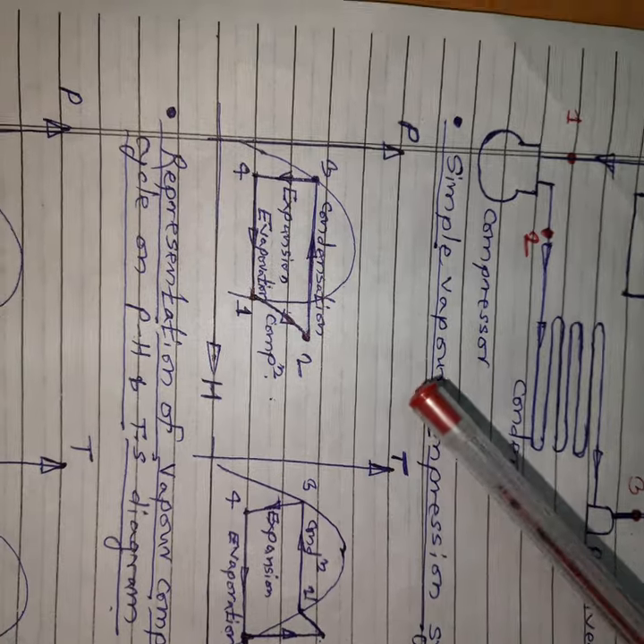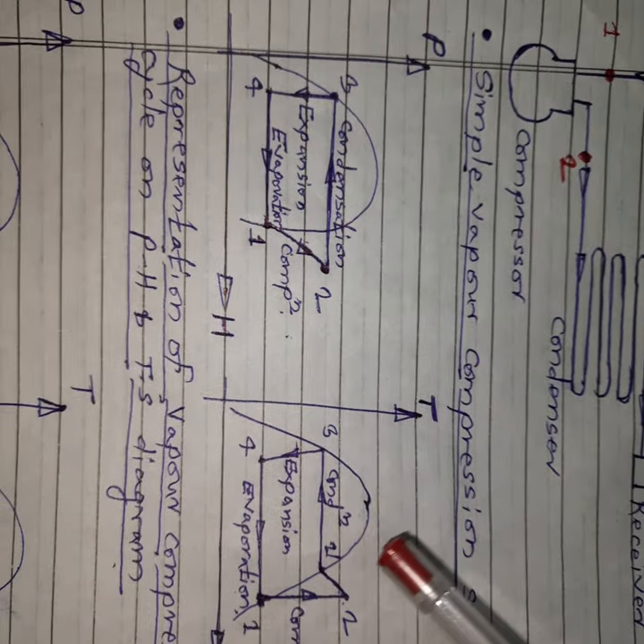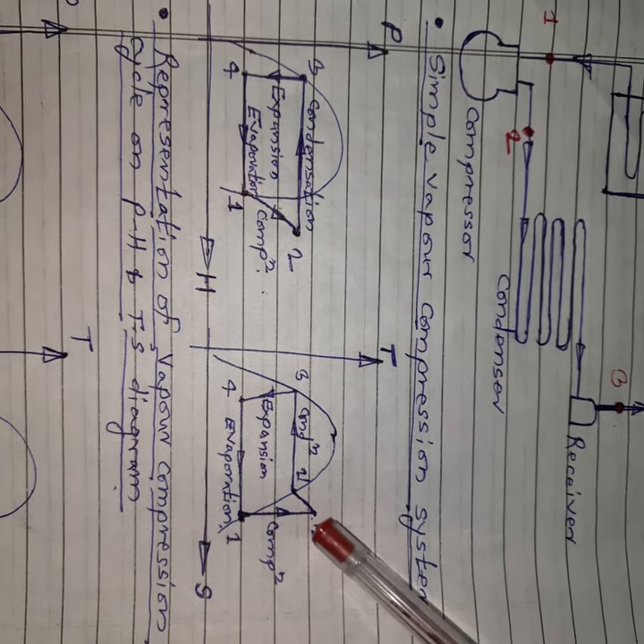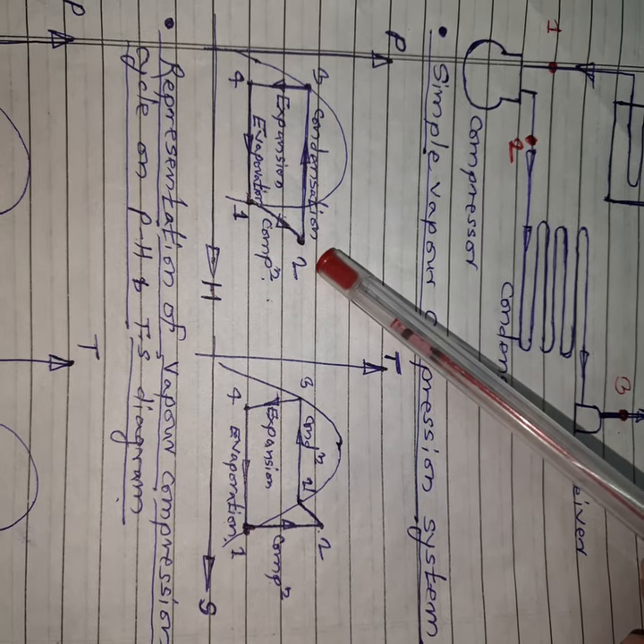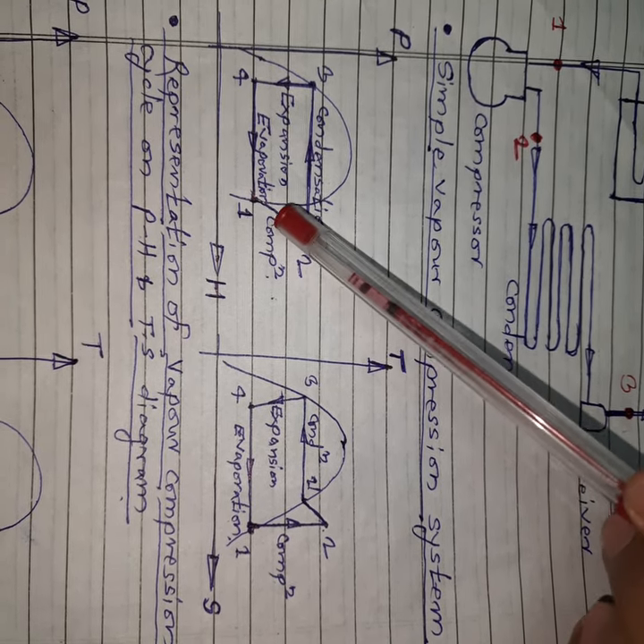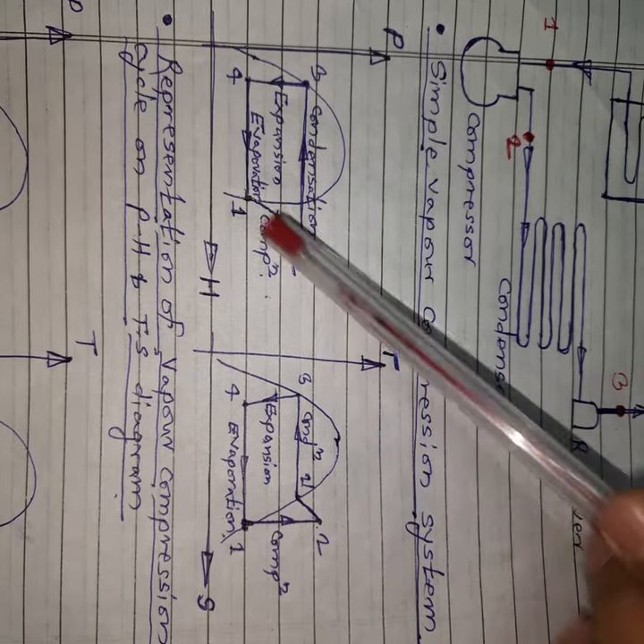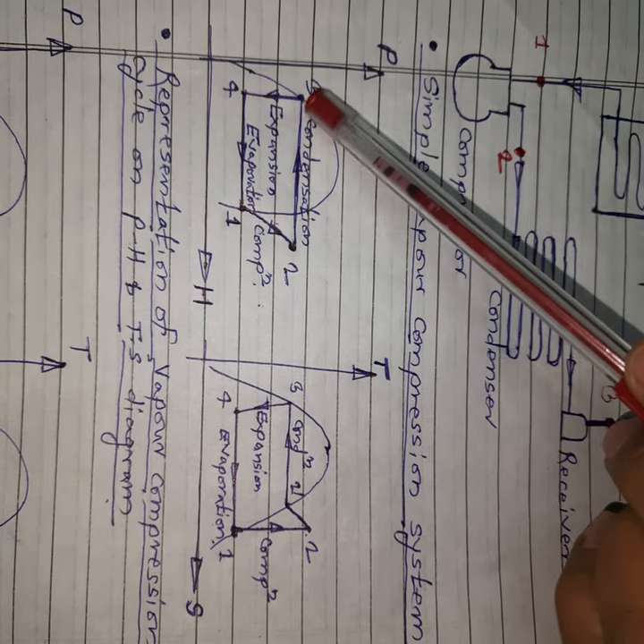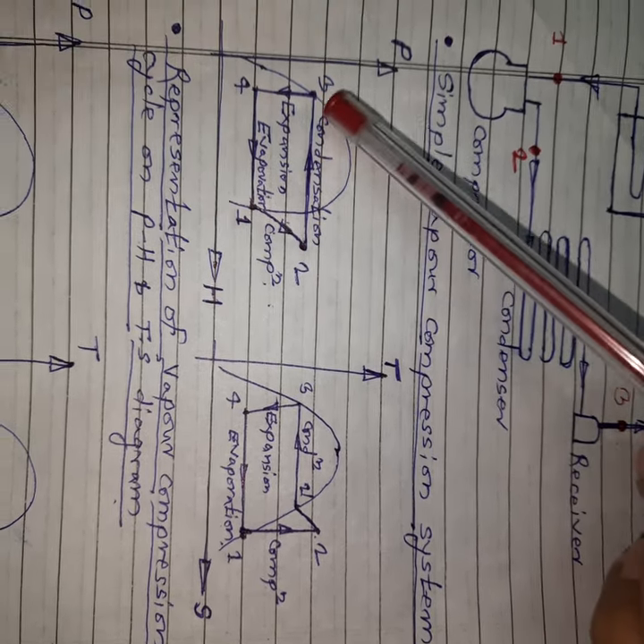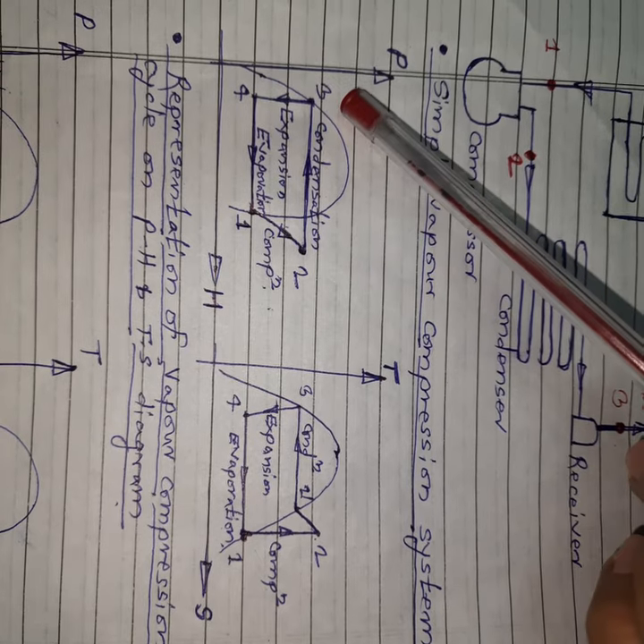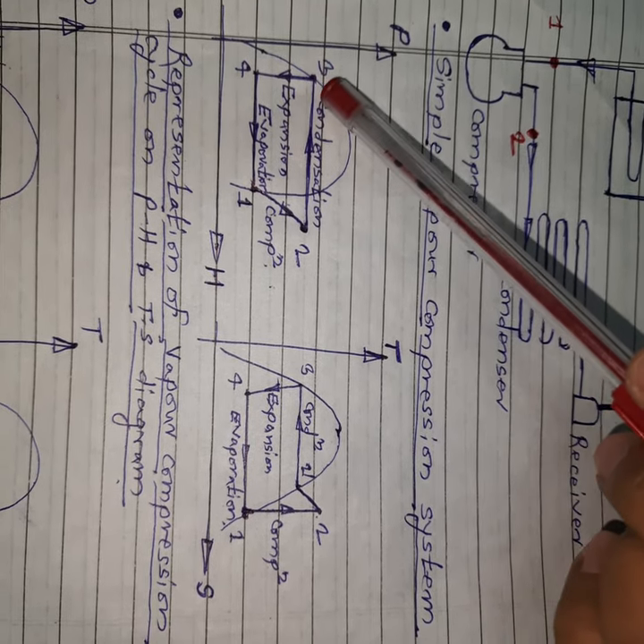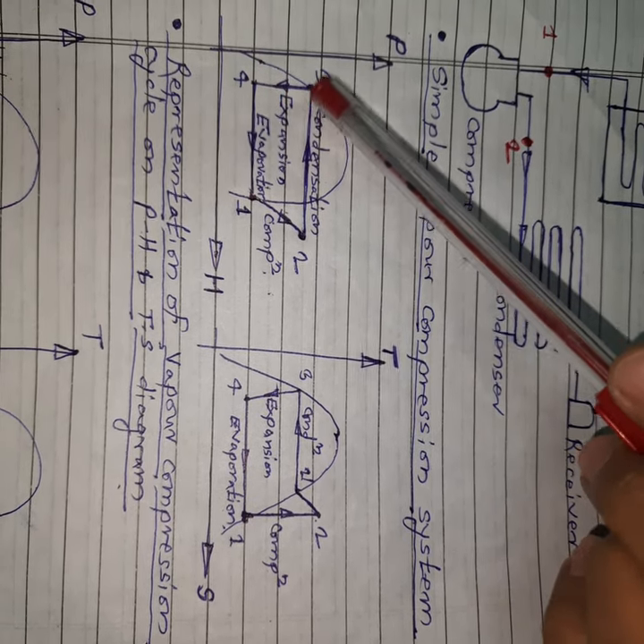This is a representation of the vapor compression cycle on PH and TS diagrams. On the PH diagram: 1 to 2 is the adiabatic compression process — enthalpy and pressure both increase, shown as a curved line. 2 to 3 is a constant pressure condensation process. 3 to 4 is the throttling process — enthalpy remains the same before and after throttling, so it is a straight vertical line, but pressure and temperature decrease. 4 to 1 is the evaporation process where heat is absorbed from the system to be cooled.